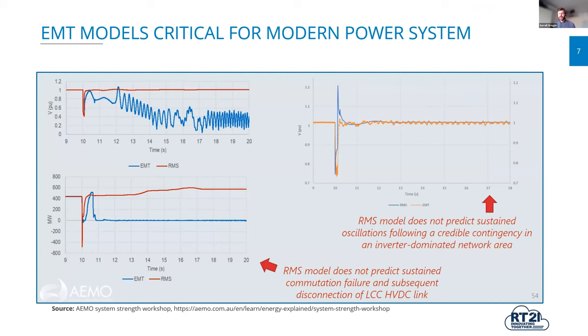To understand what all this new technology means, we need to model the system in much more detail than ever before. That's where EMT modelling really comes into form. The traditional RMS models used to understand transient stability phenomena are starting to fail in scenarios where there's a lot of inverter-based technology in one area. RMS models tend to overestimate how well things will go — for a fault, the RMS model may say 'you'll be fine' while the EMT model says 'you're in for a complete system collapse.' We've seen much greater congruence between EMT modelling results and in-field measurements, meaning the industry must increasingly shift to EMT models for transient stability analysis in inverter-dominated systems.